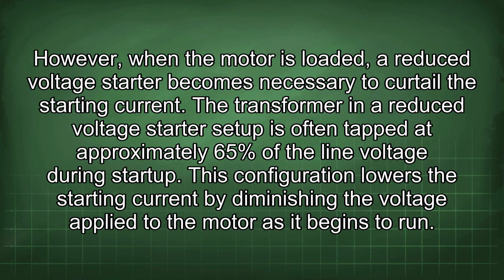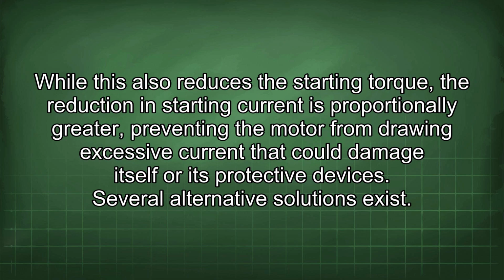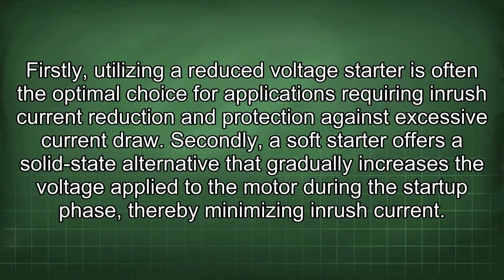This configuration lowers the starting current by diminishing the voltage applied to the motor as it begins to run. While this also reduces the starting torque, the reduction in starting current is proportionally greater, preventing the motor from drawing excessive current that could damage itself or its protective devices. Several alternative solutions exist. Firstly, utilizing a reduced voltage starter is often the optimal choice for applications requiring inrush current reduction and protection against excessive current draw.